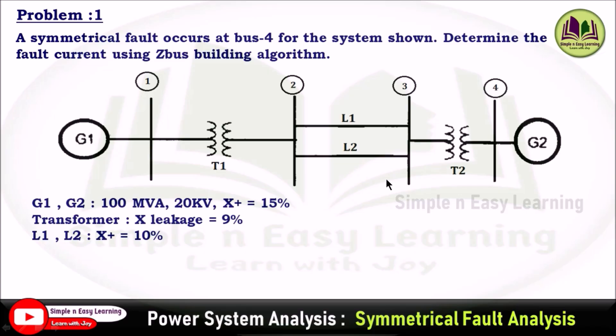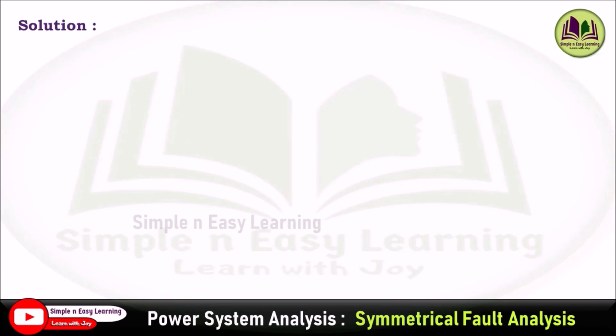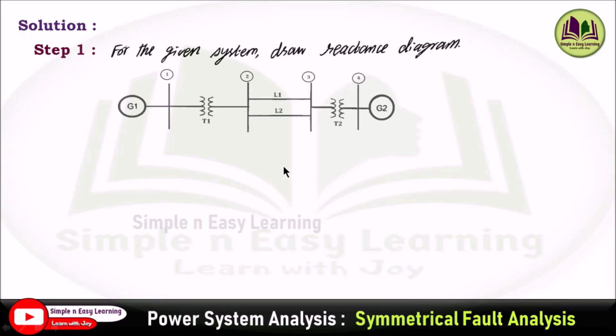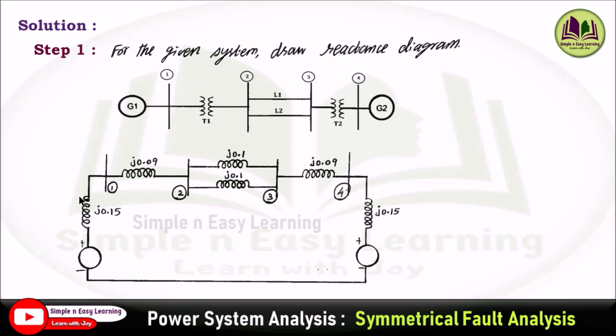Step one: for the given system, draw the reactance diagram from the single line diagram. We have a separate video for that — kindly refer to it. The reactance diagram includes generator reactance, induced EMF, transformer T1, lines 1 and 2, transformer T2, and generator G2. Values in per unit: generators G1 and G2 are j0.15, transformer T1 is j0.09, and the line is j0.1.